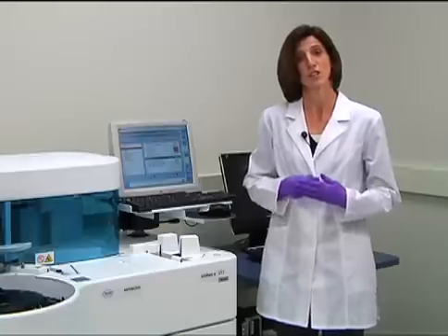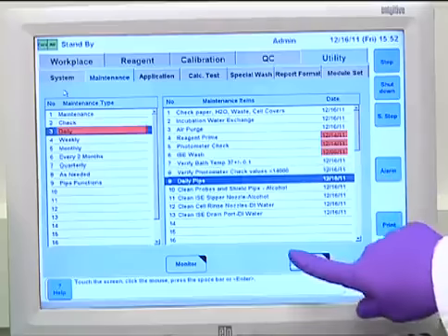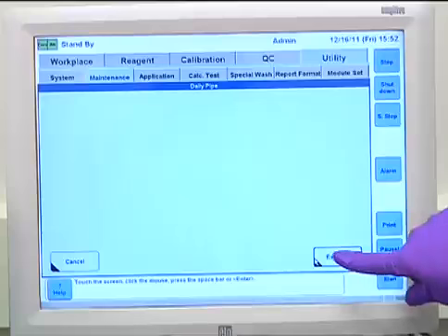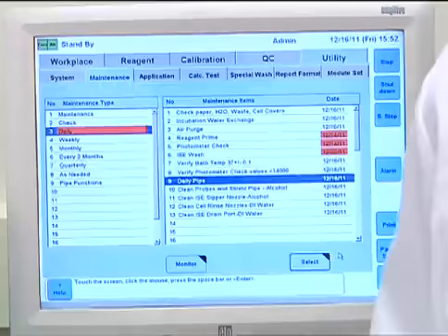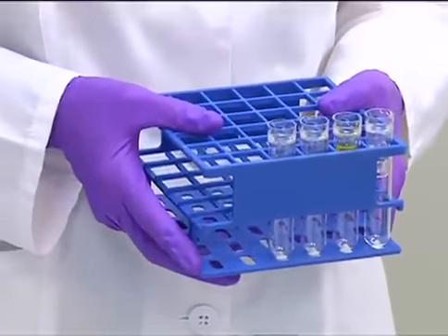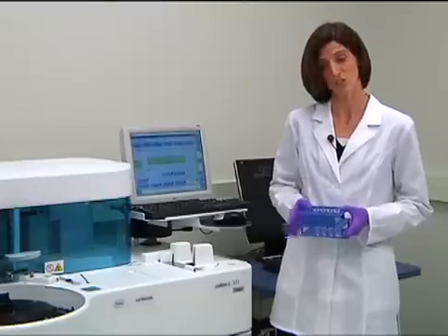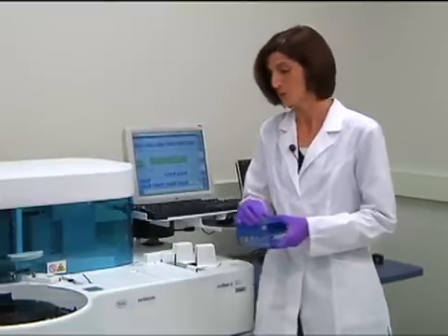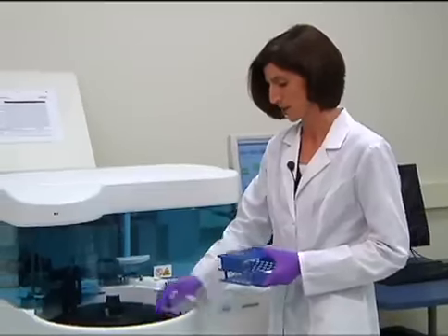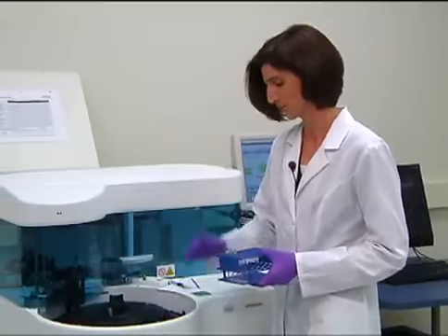If your lab is not a 24-hour lab, you can still use the pipes, and they can be utilized at shutdown and startup. That way, your maintenance is performed while you're not there. So I'm going to go ahead and execute the pipe. And while the pipe is running, I will go and gather my calibrators and controls and get them ready to run. So I've poured my required calibrators and controls, and I referred to my load list so I know what positions to place them in. So then I just simply load the cups onto the sample disc.